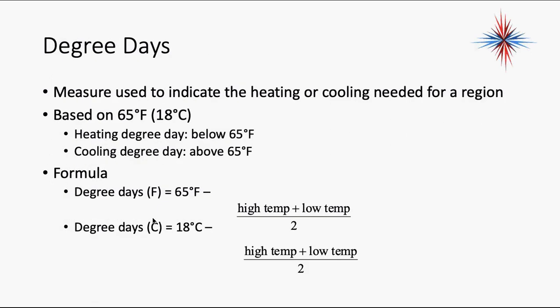So we have wet and dry bulb temperatures. You see this a lot on weather stations: degree days. This is very used in design. A degree day indicates the heating or cooling need for a region. I named three parts of the country: Albany, New York; York, Pennsylvania; and Tampa, Florida. We have different degree days in these different areas. In Albany, New York, heating degree days are basically under 65 degrees Fahrenheit, or 18 degrees Celsius. If it's above 65 degrees, it's a cooling degree day. In Albany, I'm going to have more heating degree days than cooling degree days.